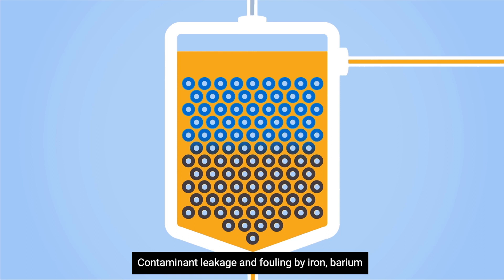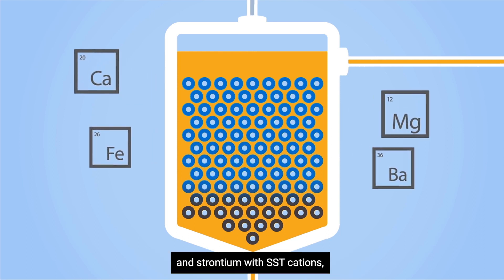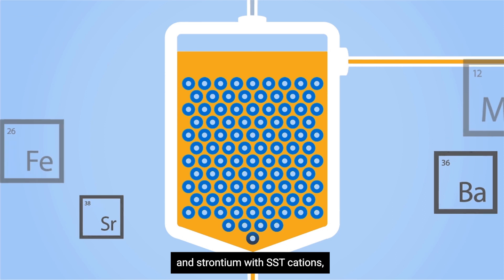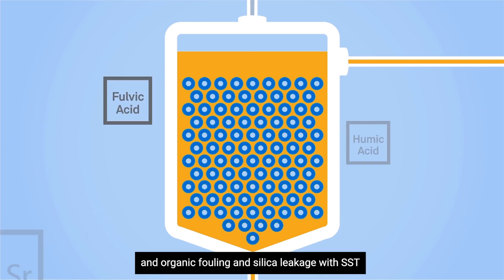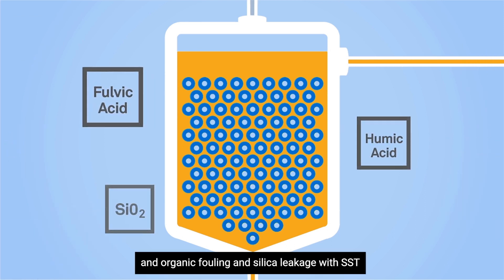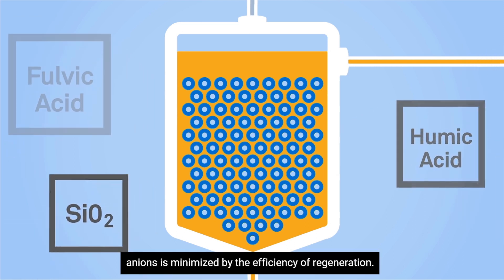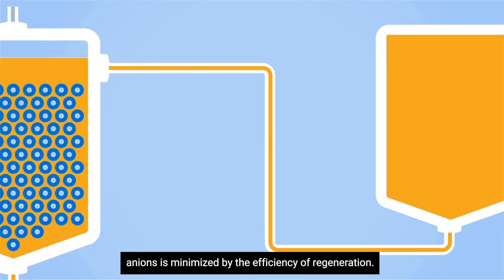Contaminant leakage and fouling by iron, barium, and strontium with SST cations, and organic fouling and silica leakage with SST anions, is minimized by the efficiency of regeneration.